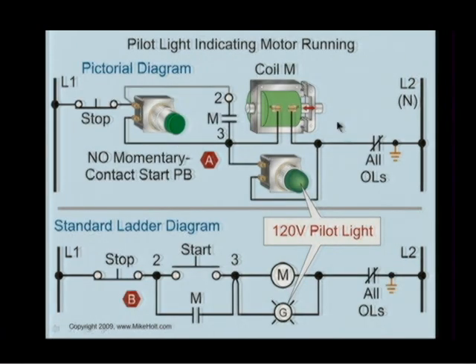Let's say application here. All right, I got line 1, I got line 2. I have voltage on this side all the way to this side. So I have voltage on one side of the coil, and I have voltage on one side of the light. I have voltage up to here, through the stop button. Voltage stops over here, and this is normally open, so that's it. All right, let's see what happens. If I press the start button, I get voltage to the coil.